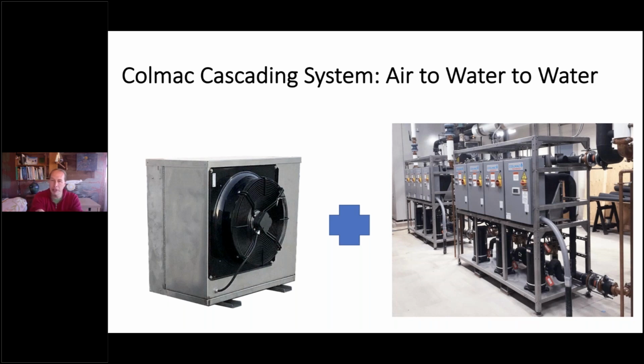And this is a classic strategy. Put some air source heat pumps up on the roof, raise the water to an appropriate temperature, 80, 100, 120, something like that. It's not for domestic hot water, it's for radiators. And then instead of cooking people the way that apartment complexes now are designed, you give everyone their own water source heat pump, with a temperature gauge on it, and then everyone can just heat their apartment as they wish instead of having everyone's windows open all winter long, which is how my sister lives with her family in New York City, on the 3rd floor, windows open all winter long so they don't just suffocate of heat.